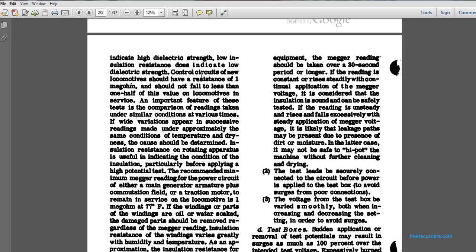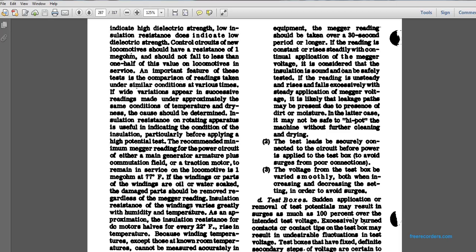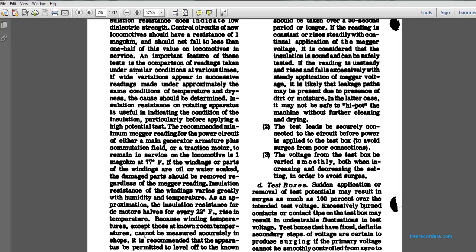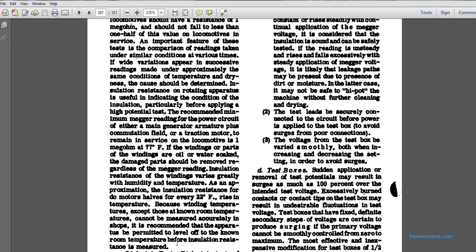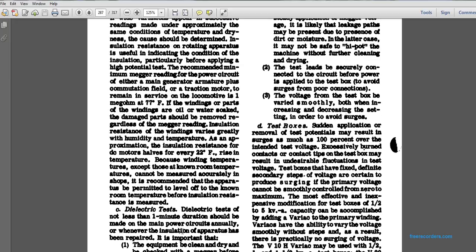If windings or parts of the windings are oil or water soaked, the damaged parts should be removed, regardless of the megger reading. Insulation resistance of windings varies greatly with humidity and temperature. As an approximation, insulation resistance for DC motors halves for every 22 degrees Fahrenheit rise in temperature. Winding temperature, except for those of known temperature, cannot be measured accurately in shops. It is recommended that the apparatus be permitted to level off to a known room temperature before insulation resistance is measured.